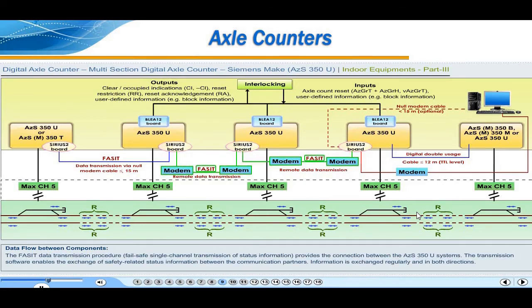The FASIT data transmission procedure, that is fail-safe single-channel transmission of status information, provides the connection between the AZS350U systems. The transmission software enables the exchange of safety-related status information between the communication partners. Information is exchanged regularly and in both directions. The FASIT data transmission method connects the AZS350U systems via a modem link, that is any length restricted only by transmission medium. Over a shorter distance, two AZS350U systems may also be connected via a cable that is less than or equal to 15 meters without modem.